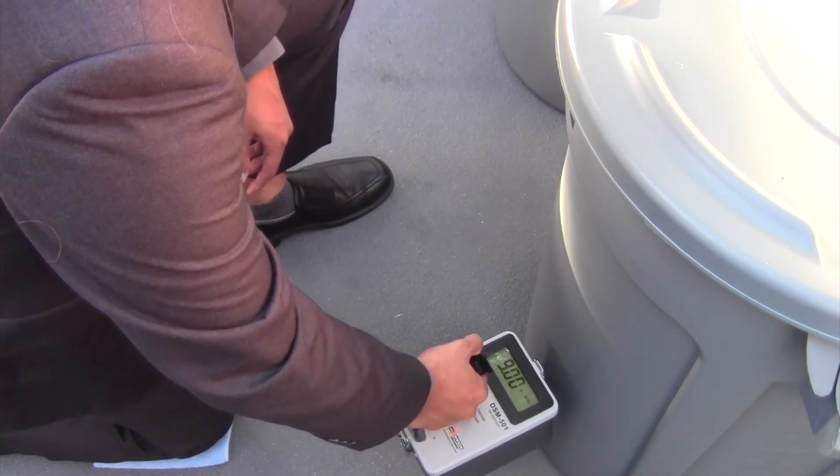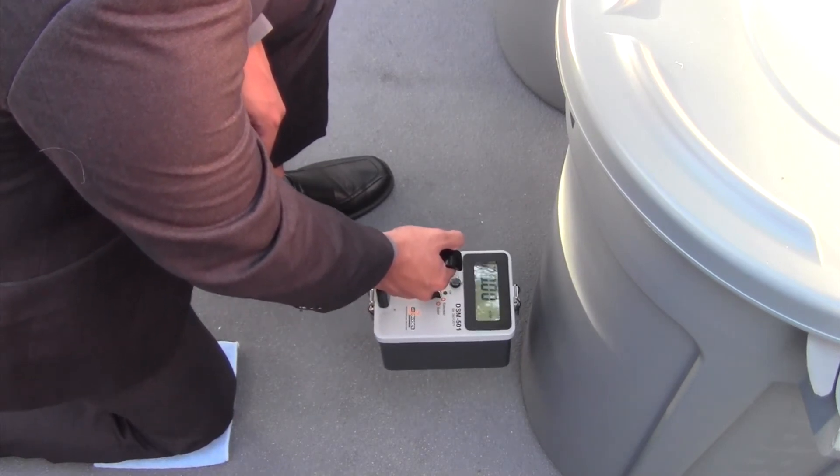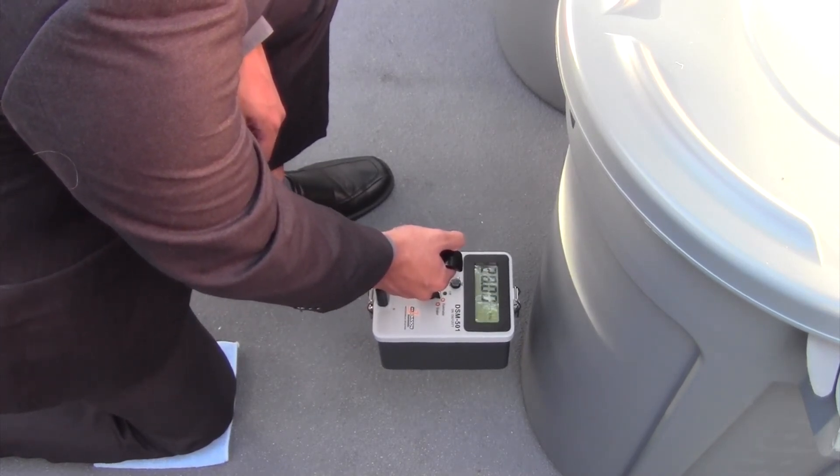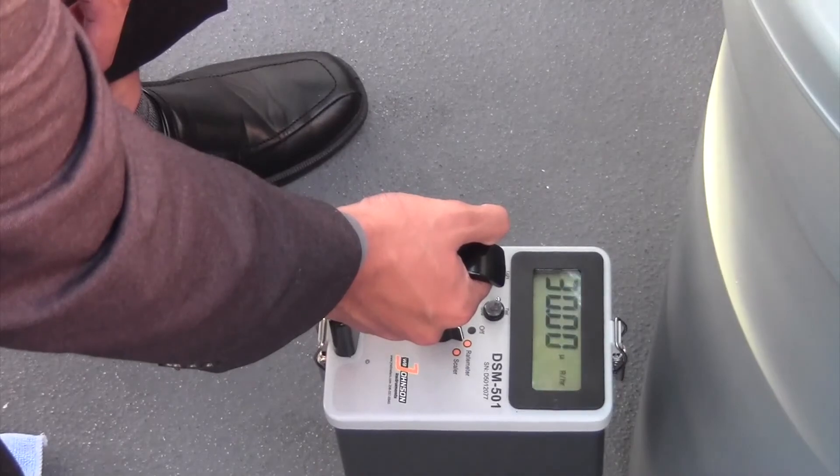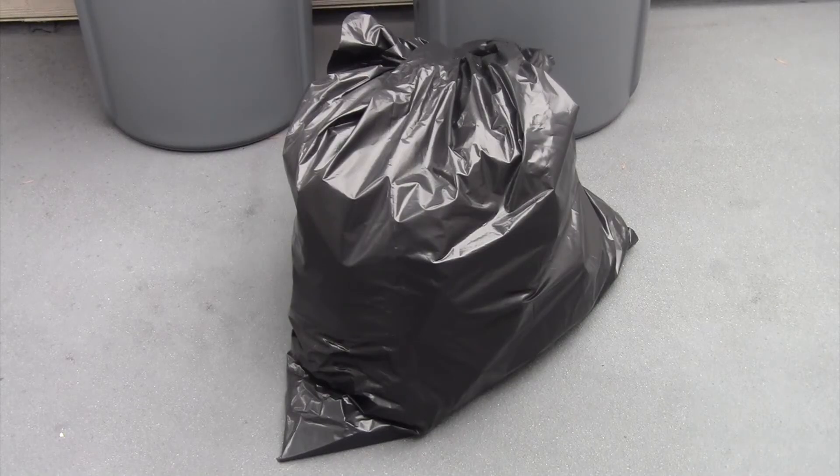If the dose rate spikes while surveying, pause for five to ten seconds over the area to provide adequate time for instrument response. After detecting a spike in radiation emission, further investigate to locate the source, which was a one microcurie cesium-137 source.